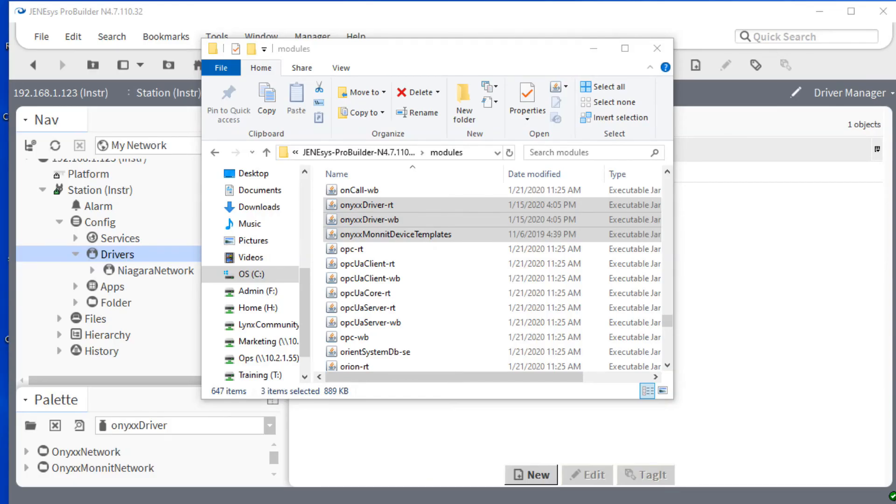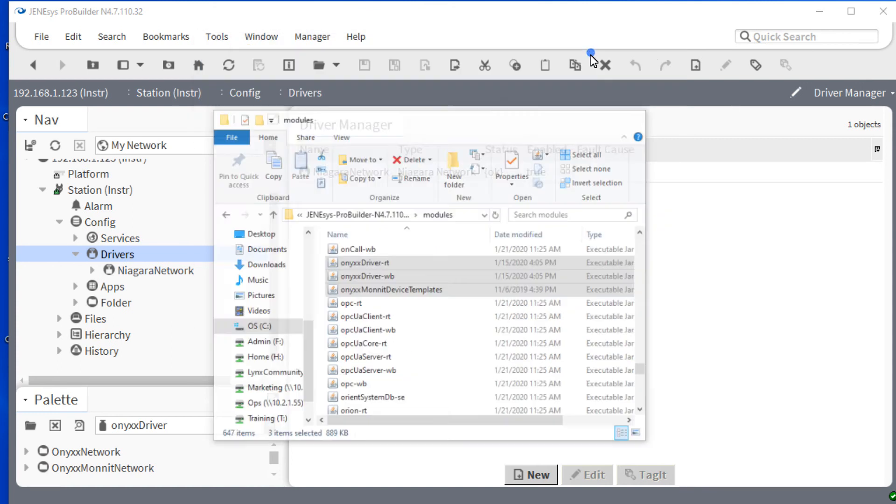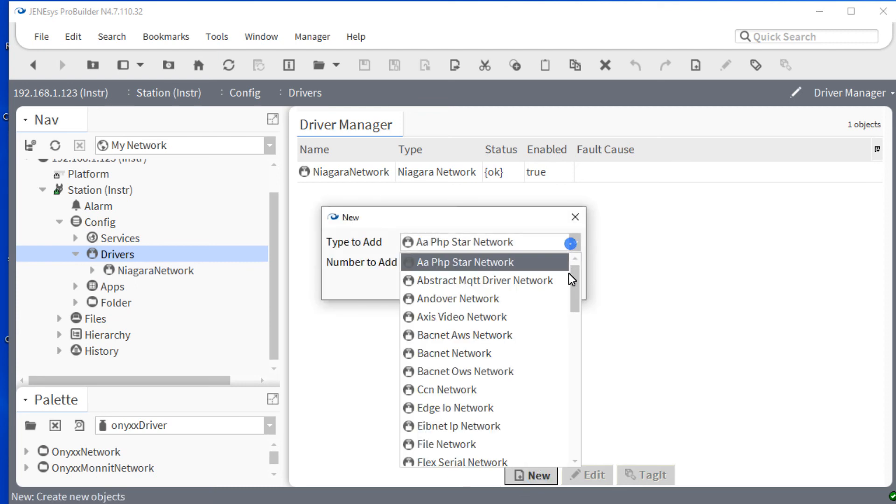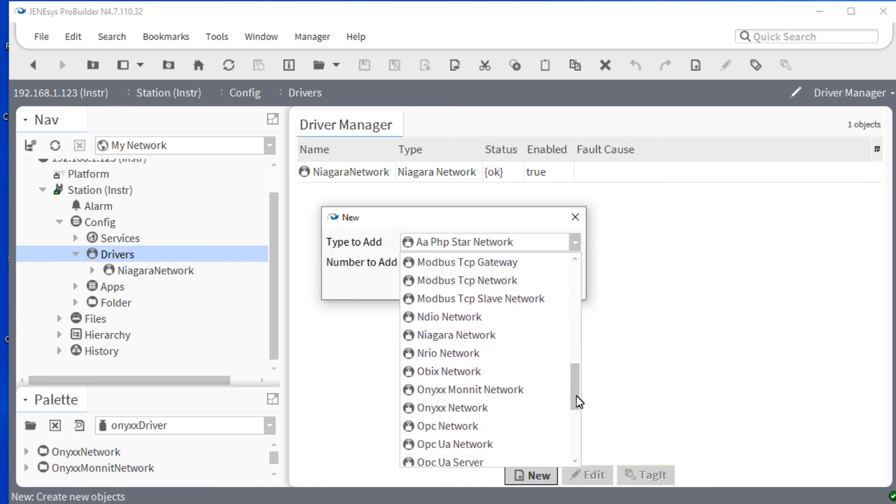Before you begin, you will want to ensure you have downloaded and installed the appropriate Onyxx drivers as well as the Onyxx Monnit device template and installed them in your install directory. You will also want to check and ensure that you have downloaded the latest firmware for your device. Once you have done this, go to the station and then under config double-click on the drivers. You may add the Onyxx Monnit network from the palette or by utilizing the drop-down in the new menu.